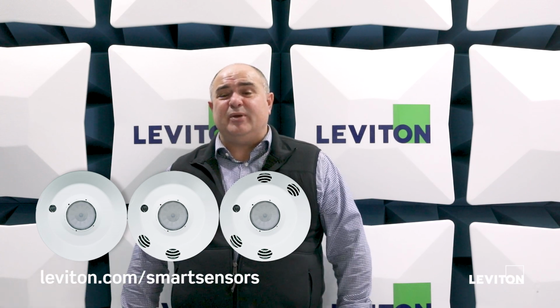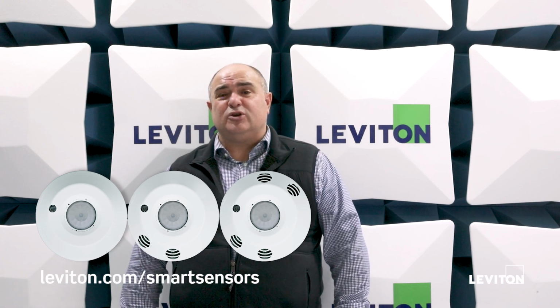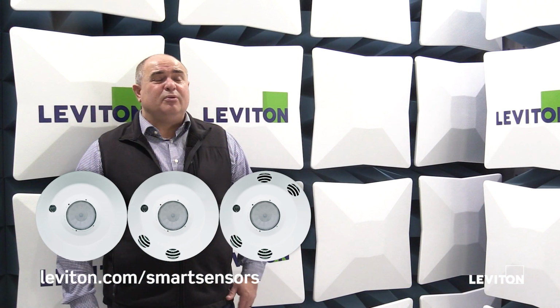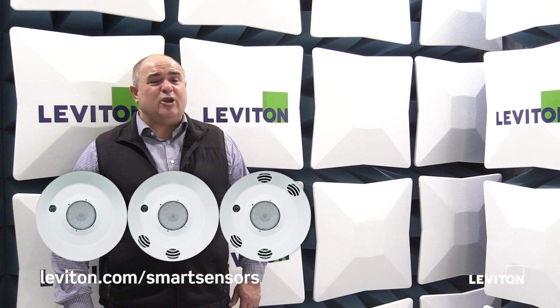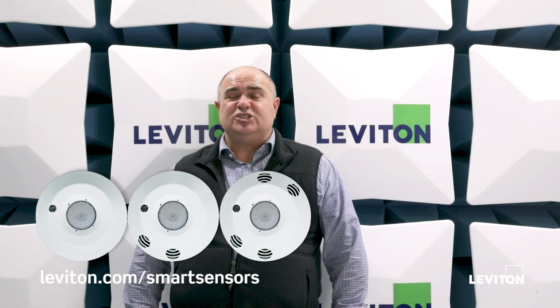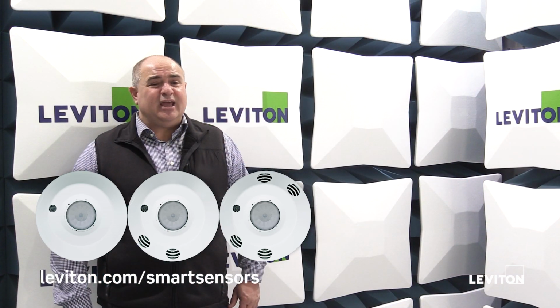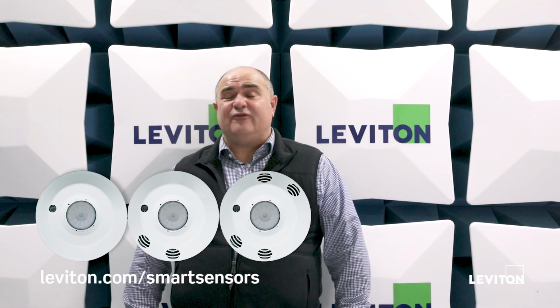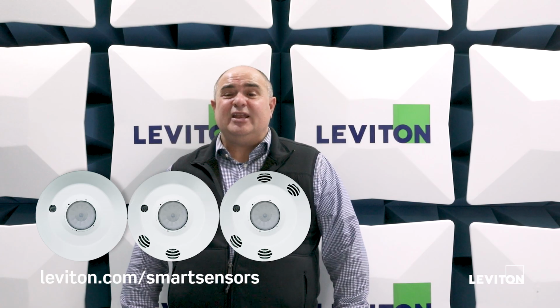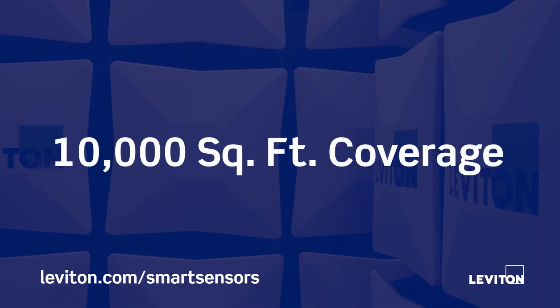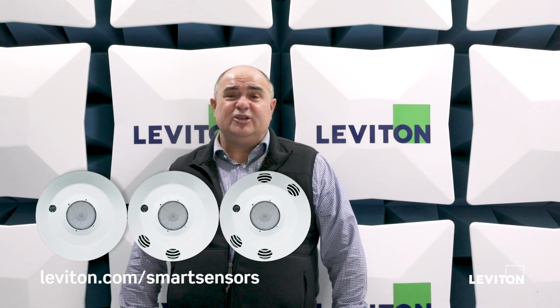Again, understanding the big difference between them: a smart room controller is truly a completely dimmable, completely daylight harvesting device, etc., where the ceiling mounted sensor is more for certain areas that just require switching. But again, we can pair up to 5 of them together to end up with an overall coverage of 10,000 square feet with this technology. Also, we can do single and dual relay models.